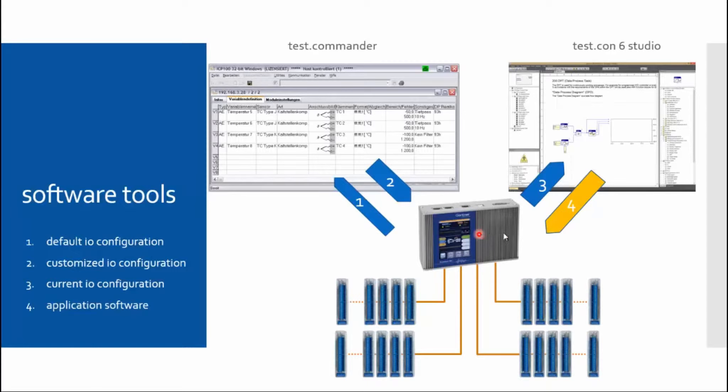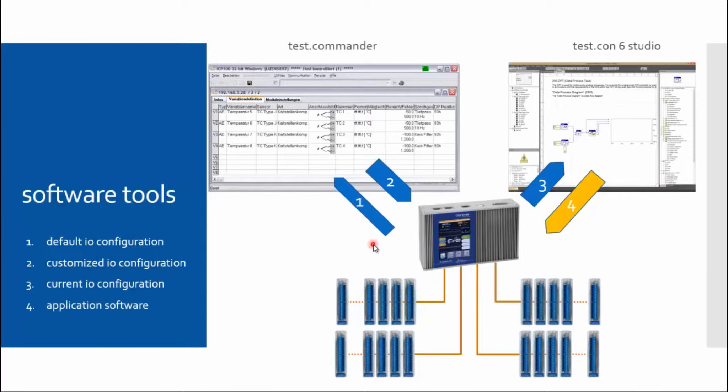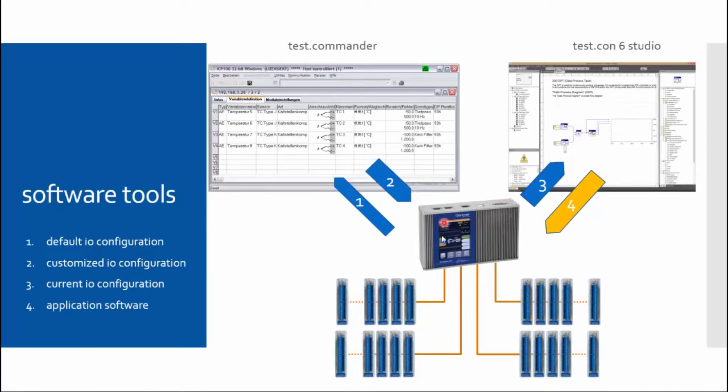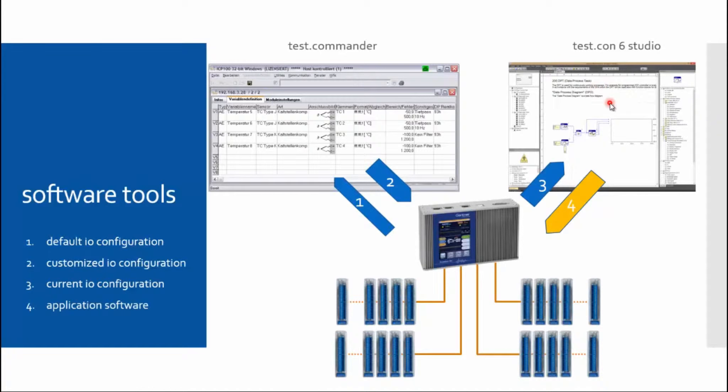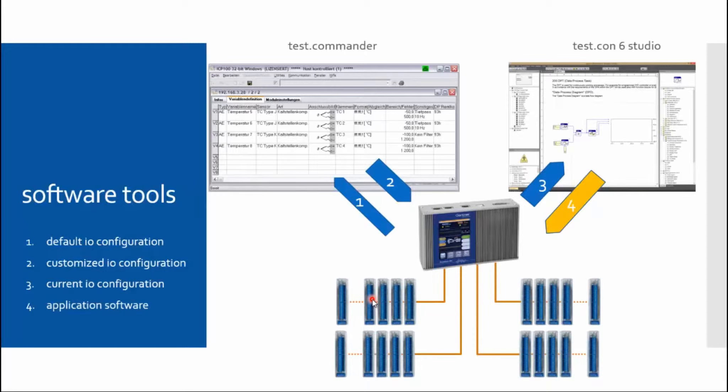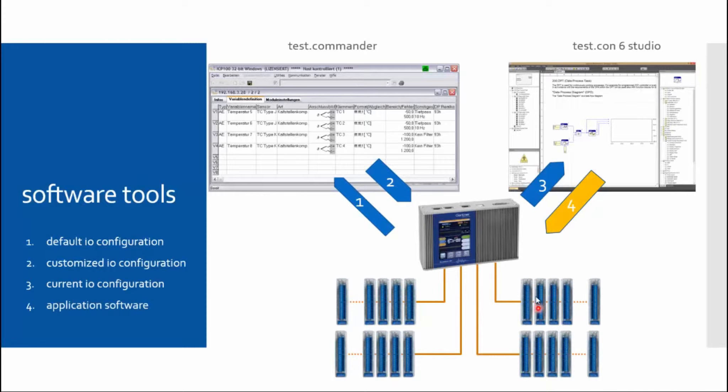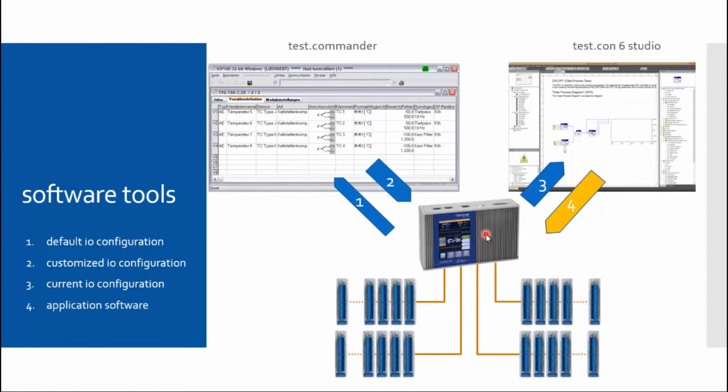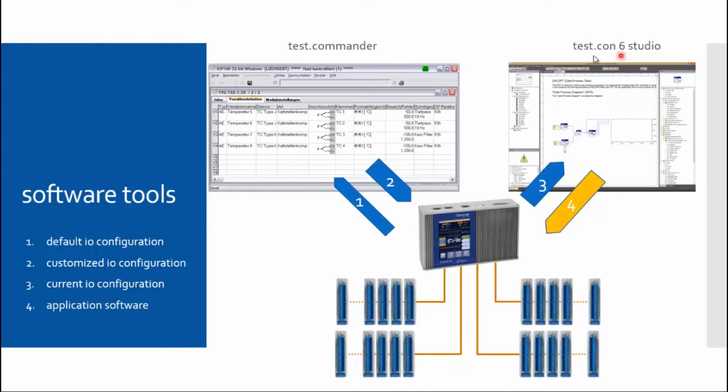If I now go on the Q.station with Test.con, I will not need the TestCommander anymore. The configuration is read directly from the Q.station. On basis of this configuration, I can write the Test.con program. Now there are specific variable names available for the I/O channels. So, for example, I know the exact channel from which temperature is read. And I can say, okay, this module here is the control input or the valve I can trigger directly in the application. That means that I write the specific application program on the basis of this configuration. This program will then be downloaded on the Q.station and it can work autonomously and independently. So the execution order is to first create a configuration in TestCommander and then program the application with Test.con.